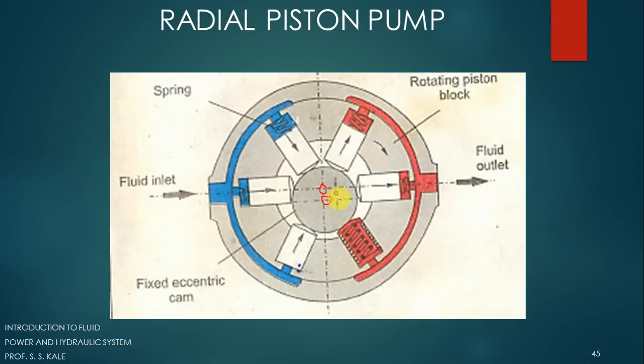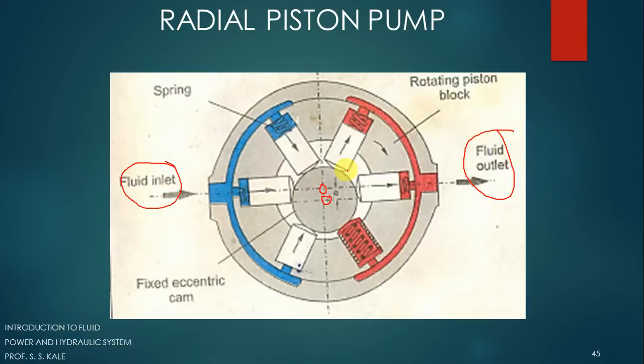This eccentricity is very necessary to move the piston forward and backward. These pistons are provided in the cylinder cavities. Three cylinder and piston arrangements are connected to the inlet port, and three are connected to the outlet port. Because of eccentricity, some pistons will be moving toward the center and some away from the center.